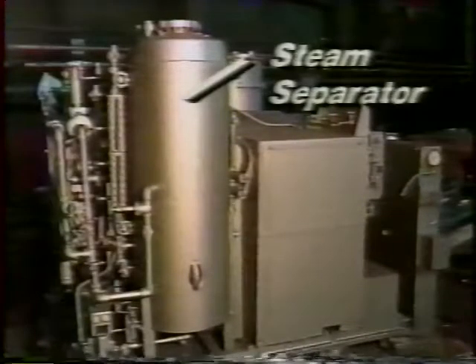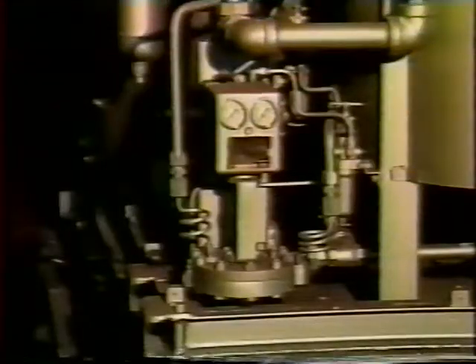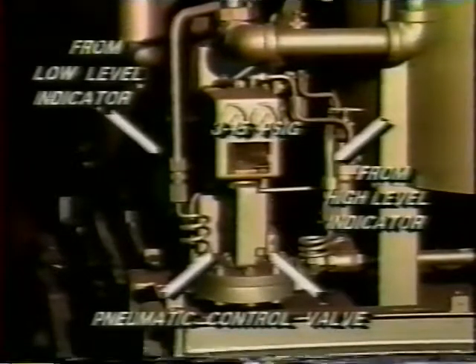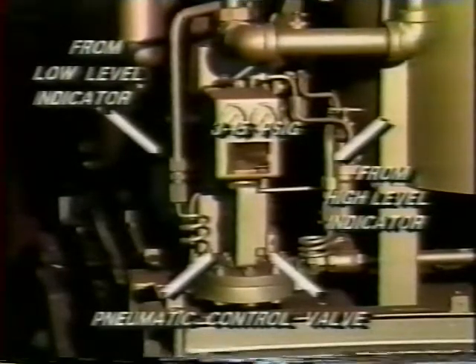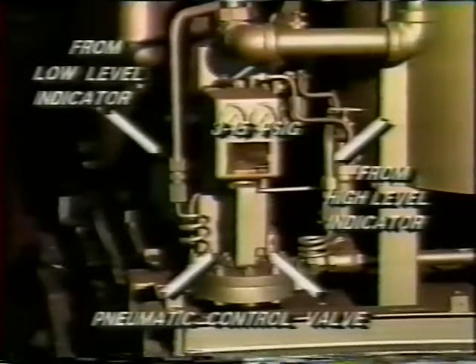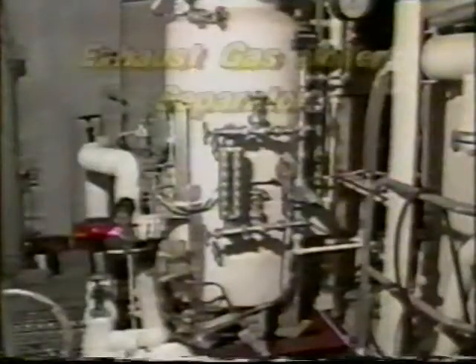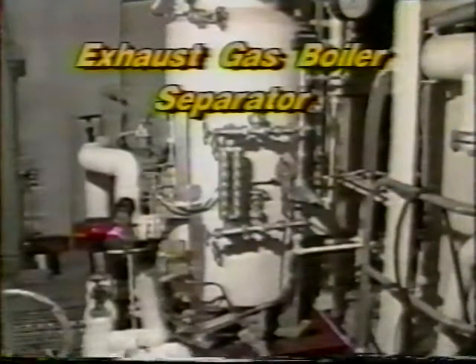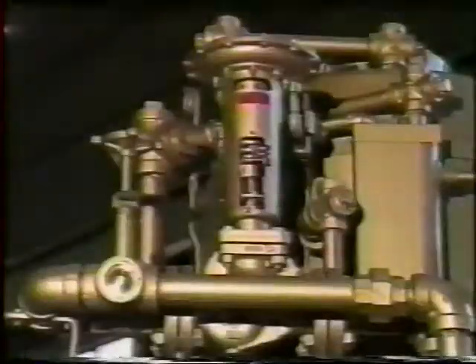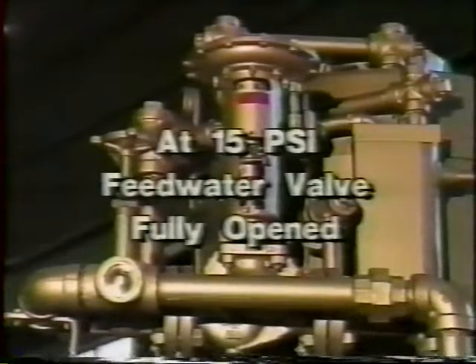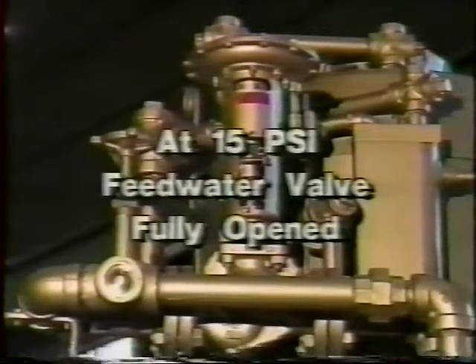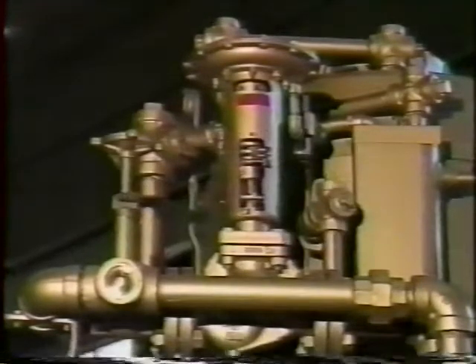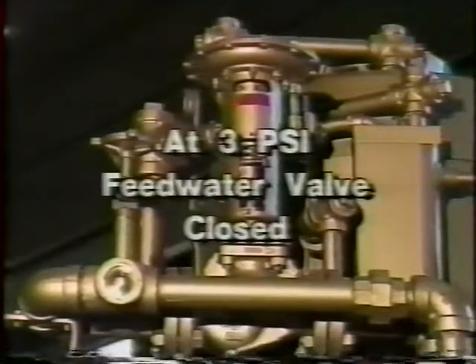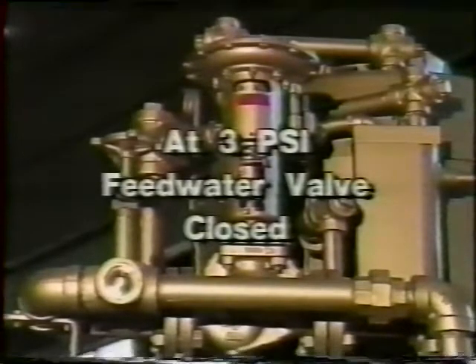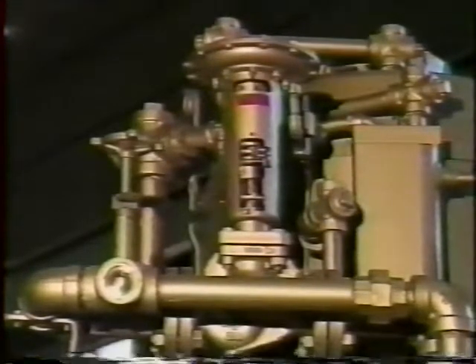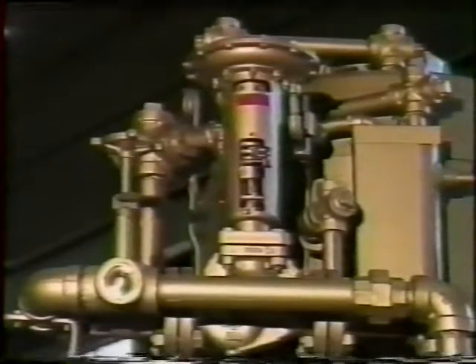Water level control in the steam separator is maintained by a liquid level control, which creates a 3 to 15 psig pneumatic signal to a pneumatically actuated control valve. This system operates identically to the system found in the waste heat boiler. On a high air pressure signal of approximately 15 psi, the feed water valve will be fully opened. On a low air pressure signal of about 3 psi, the feed water valve will be closed. On pressures between 3 and 15 psi, the valve opening will be modulated.